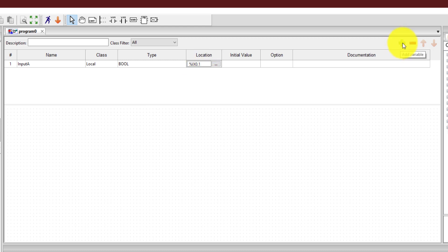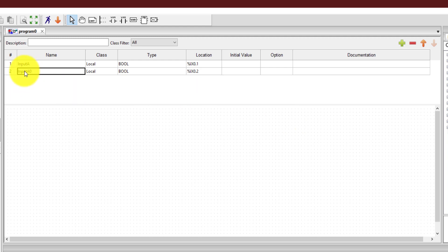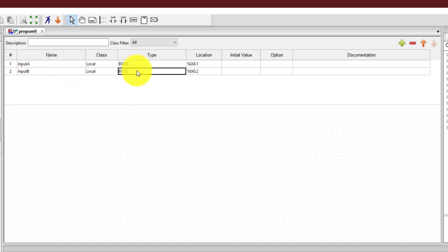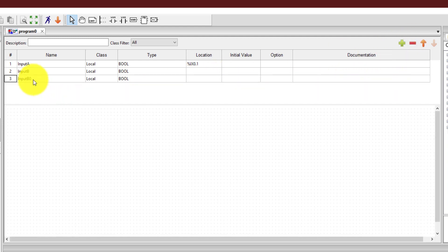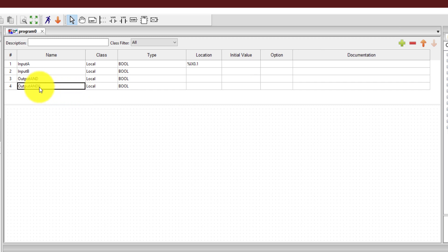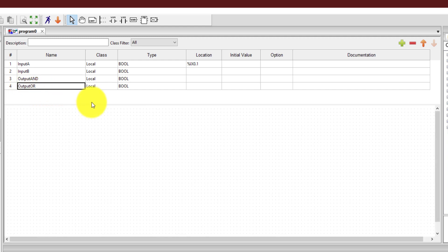Now I want to add another variable. I'm going to click over here. That variable is automatically named as A0, but let me change it to input B. The type would be Boolean. I can delete this location because I know that this program is not going to connect to any physical hardware, so I don't need that location. Now for the third variable, it will be an output. I'm going to name it as output AND and use it for the output of the AND gate. The fourth variable will be an output for the OR gate, so I've named it as OR. Now I have created all the inputs and outputs required for the program.